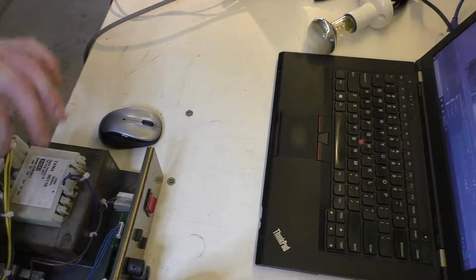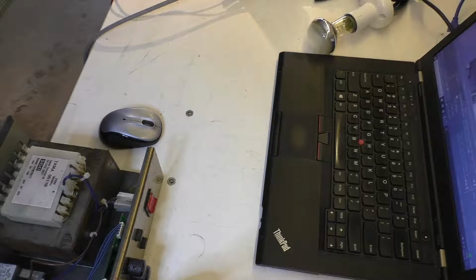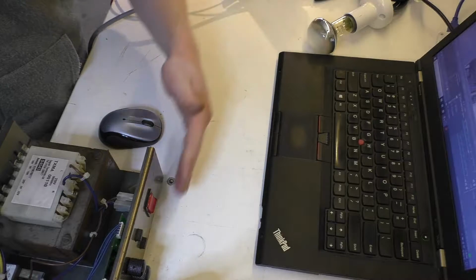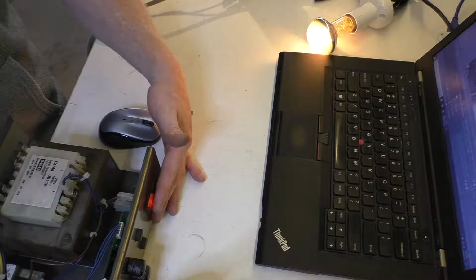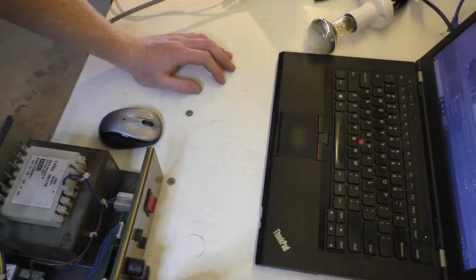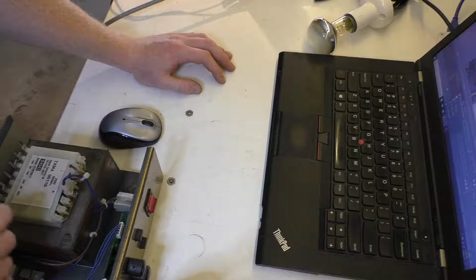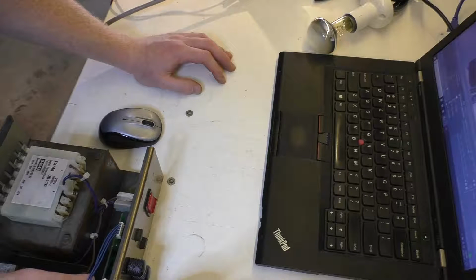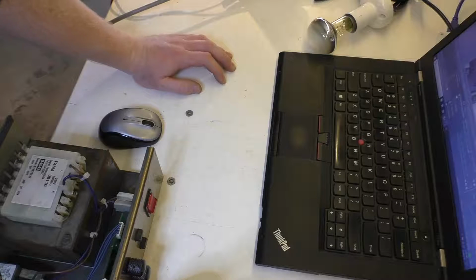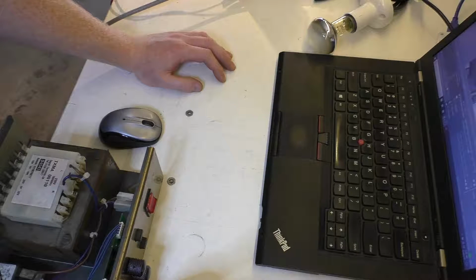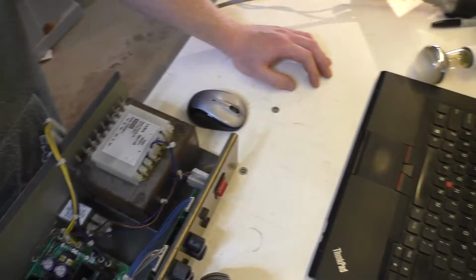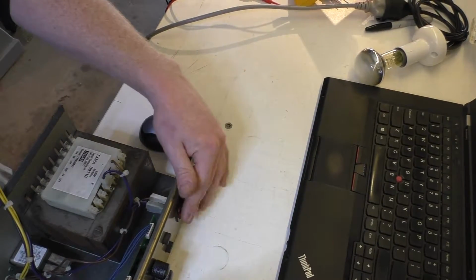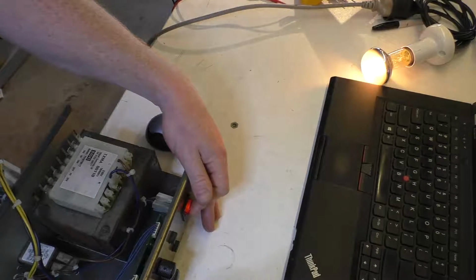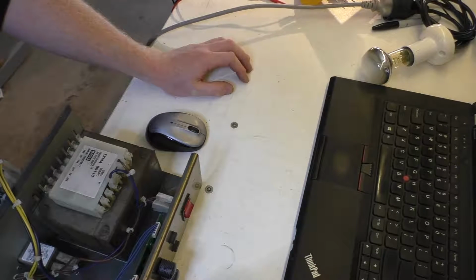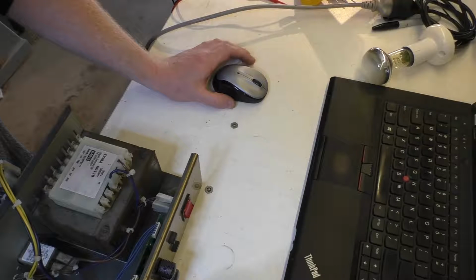Let's isolate the secondaries. Literally the only thing the power is going into is the primary of the transformer, and we'll see what it does. Interesting. That's not good. I think that transformer is gone. It's running, but that's drawing way too much current for an isolated transformer. That's almost full on. Alright, so what caused that?